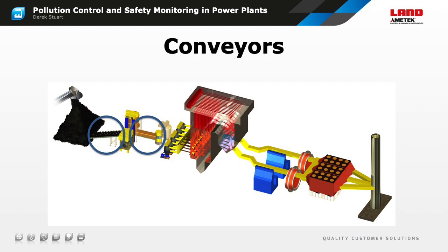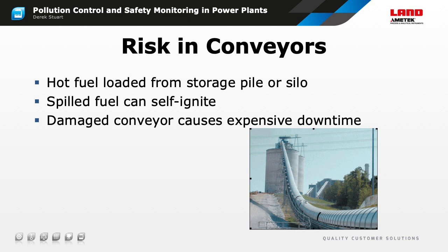Conveyor belts are used at many points within a power plant. They're also used in pellet production and shipping facilities. If we can detect a small amount of smouldering material on a belt, it can be diverted or extinguished before it's loaded into a silo or onto a ship, where it can ignite a much larger amount of fuel and cause serious damage. We have a quite specific set of issues in detecting spontaneous combustion in material on a moving conveyor, not least that it's moving rather fast. In addition to the danger that it poses to plant and personnel downstream, hot material can damage the conveyor itself and cause expensive downtime. If a conveyor can't transport fuel to the boiler, the plant can't generate electricity.